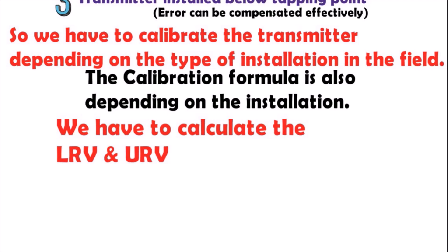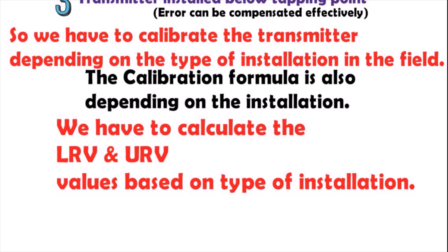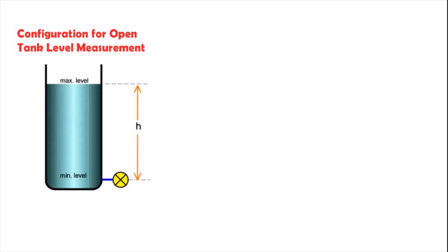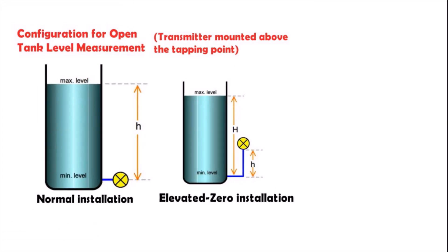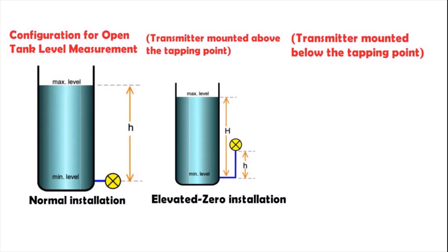We have to calculate the LRV and URV values based on the type of installation configuration for open tank level measurement. Let's look at this: there is one height minimum and maximum level - this is normal installation. The second case of installation, transmitter mounted above the tapping points, has two types of heights - this is elevated zero installation.